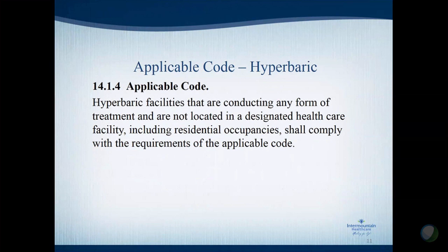Right? So that sounds like we're saying the same thing over and over again. But we're really not, because it's a technicality. NFPA 99 may not have been adopted in your area, and Utah is one of those. But there is no other chapter. And CMS and Joint Commission do refer to Chapter 14. So by default we are the only chapter out there. If your state or local authority is not using NFPA 99, this gives them the permission to use it because we're using that language.